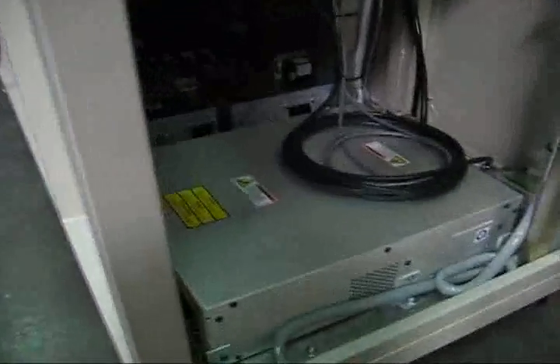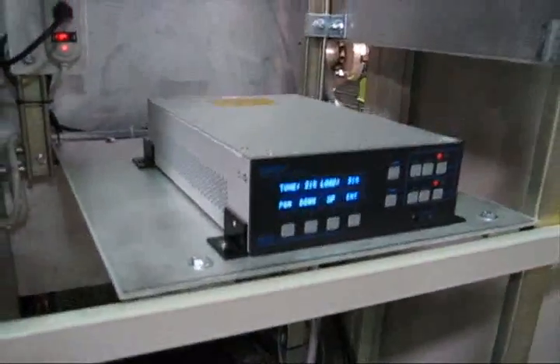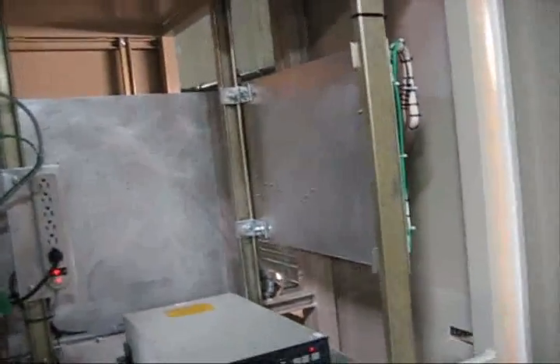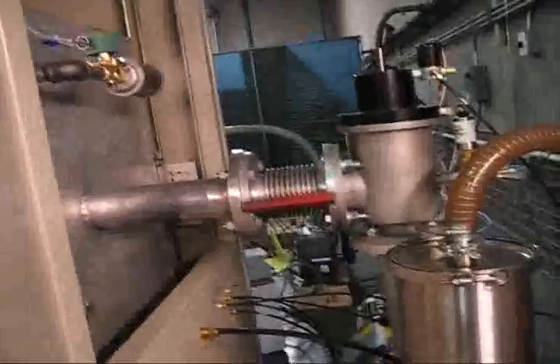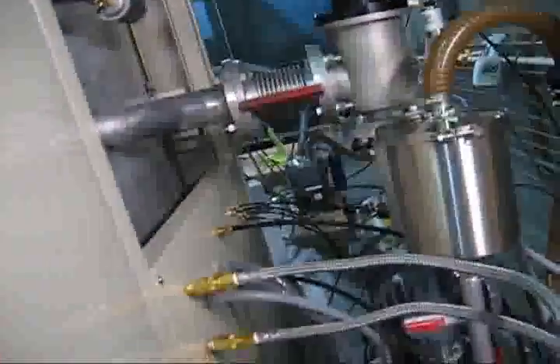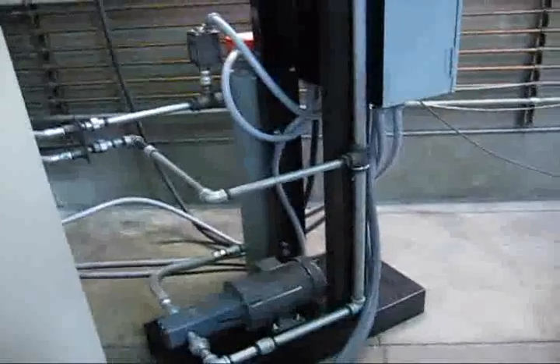Down below, that's our RF generator, solid state, water cooled. Up here you can see we have a matching network. PLC controls are in the back here, a little tough to see, but they're there. Okay, we take a quick tour around the back. This is our vacuum pump. That's our PLC again. On this side here, we've got temperature control and all the power controls for the unit.